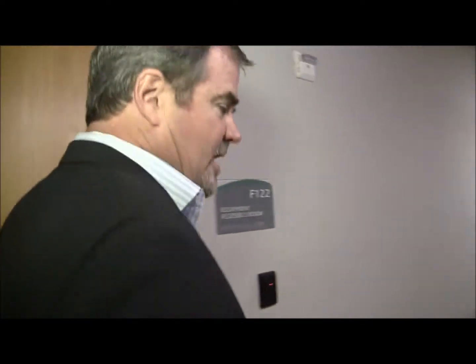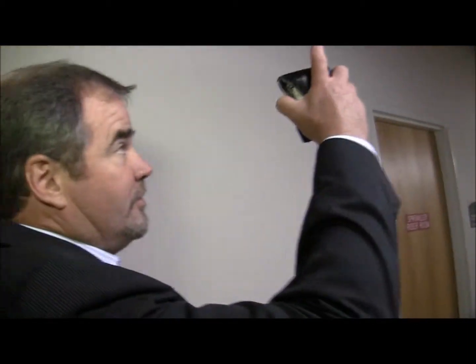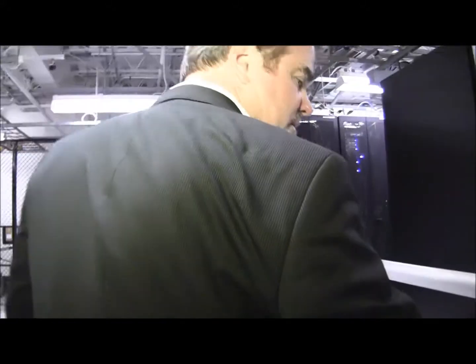The data center itself is on each floor. We have 2 floors of the building. It's an 18-inch raised floor, and all of the facilities that come out to the floor, through ladder rack for fiber and cable for Cat5, are delivered overhead then down into the cabinets. We have cage and cabinet configurations. Our largest customer here is 2,000 square feet on this floor. And then our smallest customer, we actually sell quarter cabinets, some 1 and 2U applications, but generally as a convenience to people for gear that they want to use as out-of-band management. It's not a commercial product for us.